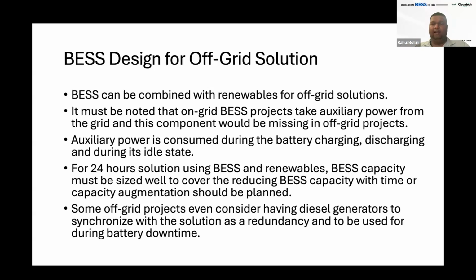There are also some projects where people are concerned, or one should be concerned, that with time the battery capacity reduces. Typically, if you're doing a 24-hour project where solar operates throughout the day and the evening needs to be covered by BESS, as the battery capacity goes down with time, the backup hours would reduce, and there's a small gap of energy not being there. So at that time, typically in countries - at least I've seen in off-grid Middle East projects - people tend to synchronize a diesel generator through a voltage synchronization part, using some switch and all. That is an option. Or I suggest go for augmentation. Either way works, but you need to keep this in mind.